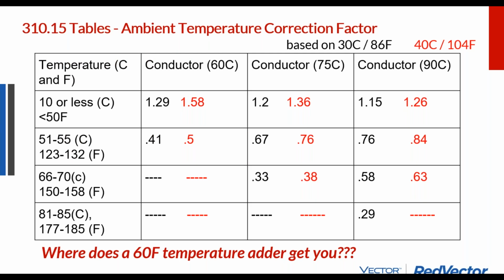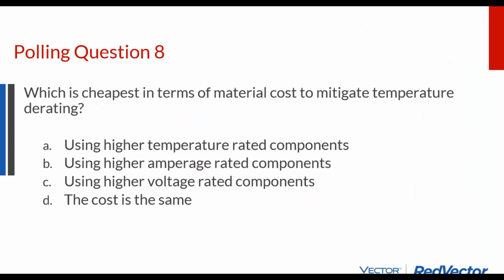The main thing that we aren't going to have time to cover is the temperature correction chart, which is, if you're using cables that are rated for a lower temperature, but you're using them in a higher temperature environment, how do you derate them to make sure you don't burn your conductors up? And the derating factors can be rather substantial, 60%, 40%.